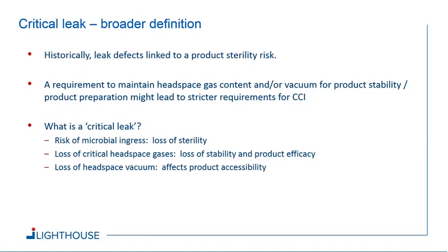And you can ask yourself, what is a critical leak for my product? Obviously, for all sterile product, the risk of microbial ingress applies across the board. You have to keep your product sterile. For other product that may react with reactive gases such as oxygen or water vapor, moisture, the loss of critical headspace gases can lead to a loss of stability and product efficacy. And for the patient, of course, this is just as much a risk as microbial contamination.